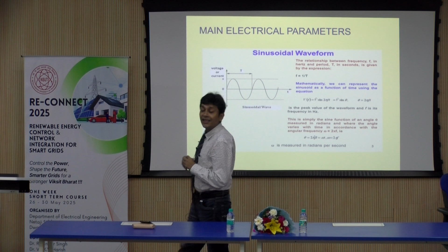Coming back to the very important fundamental things. When we talk about power systems, they revolve around only 3 important parameters. I am repeating, only 3 parameters: voltage, current and frequency. When I say voltage, you have to take care of the system voltage, overvoltage, transient voltages and lightning voltages, and you have to provide proper clearances and insulation for this very first part. Then comes current. When I say current, you should have sufficient capacity of conductors to take care of your regular requirement, overloading requirement and short circuit requirement.